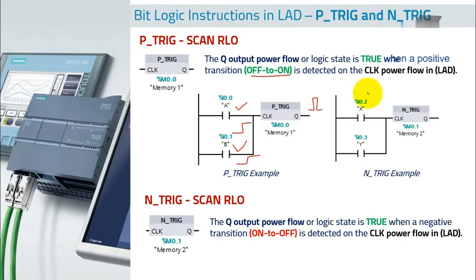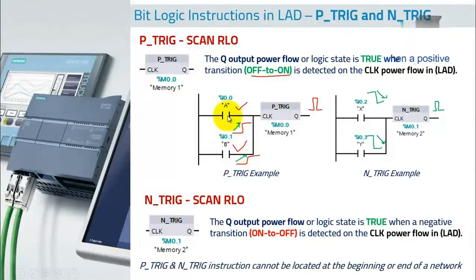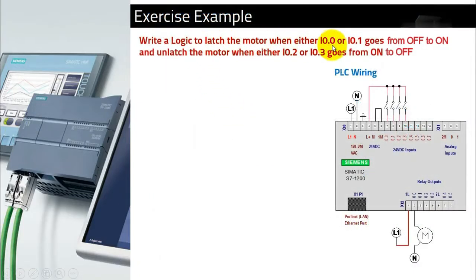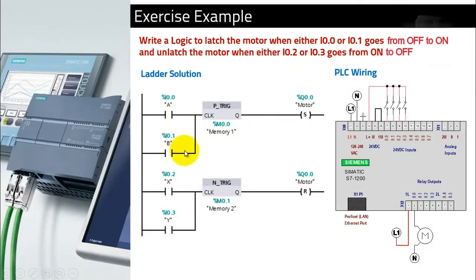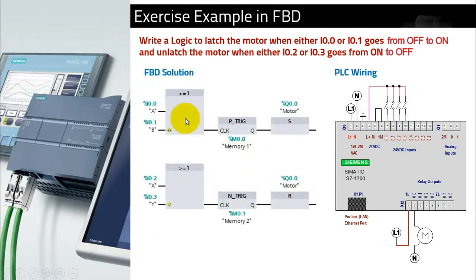For example, with two inputs A and B — I0.0 and I0.1 — connected in parallel and fed into the P-trigger, you get a pulse if either input goes off to on. Similarly, the N-trigger gives a pulse on on-to-off transition of the RLO. The difference is: the positive/negative edge contact detects a single operand, while P/N trigger operates on the result of a logic operation.